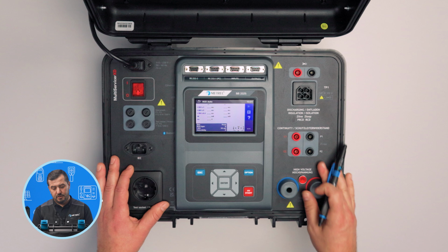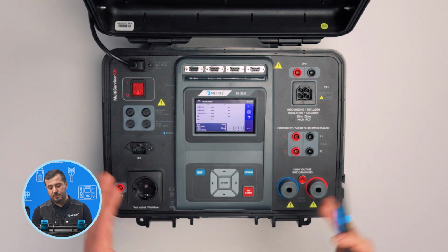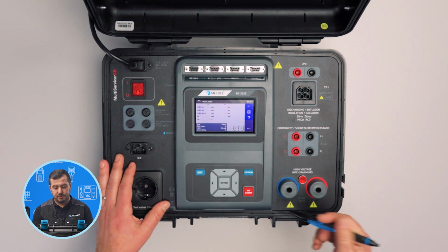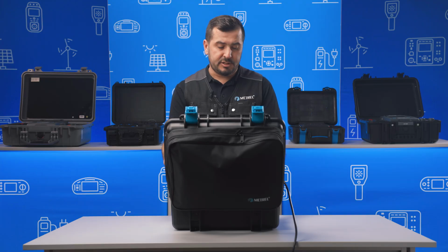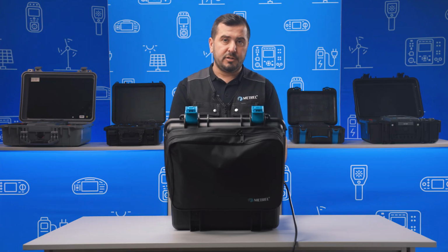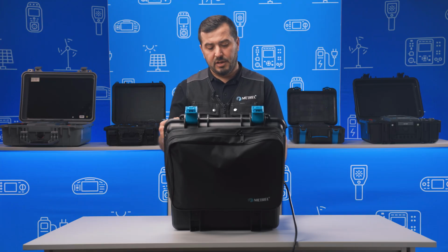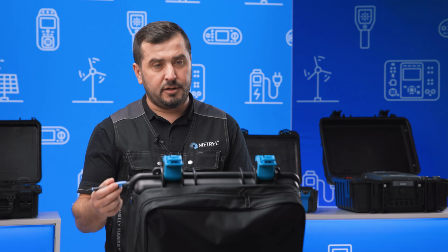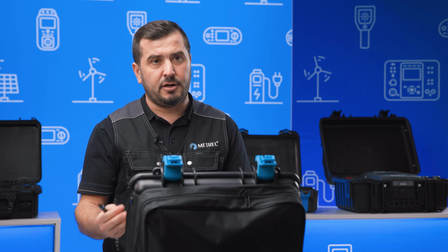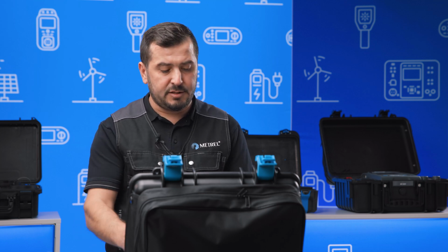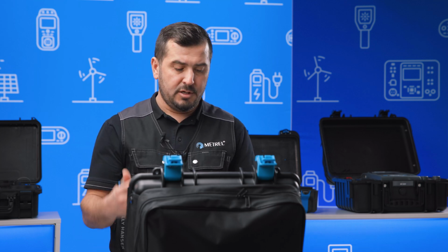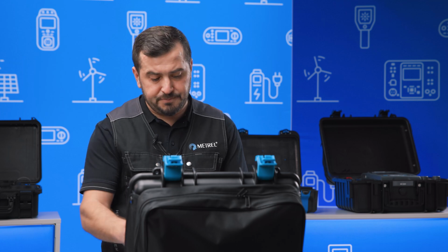Then we have the auto function. This one is quite appropriate if you want to do things fast, because in one measuring step we will measure the trip out time of the RCD at nominal current, then at 5 times the current and at half of the current, plus at the end we will also measure the ramp and the contact voltage.